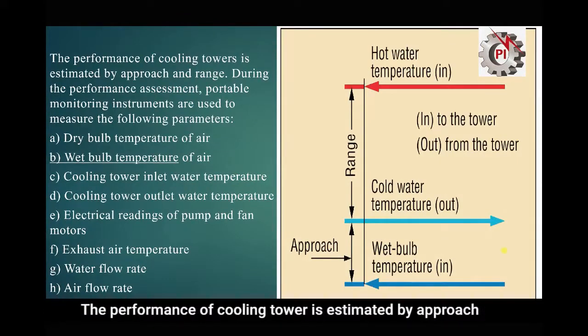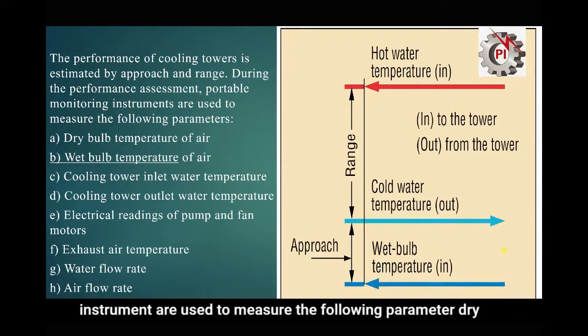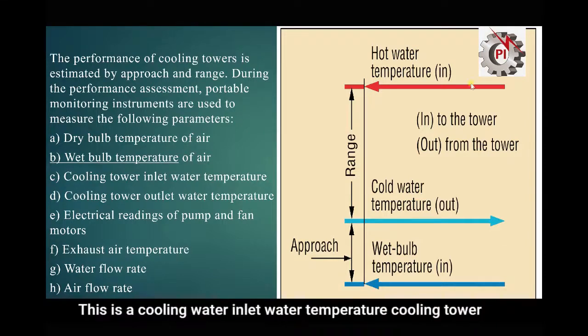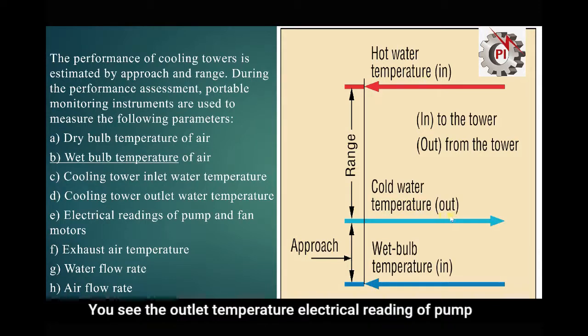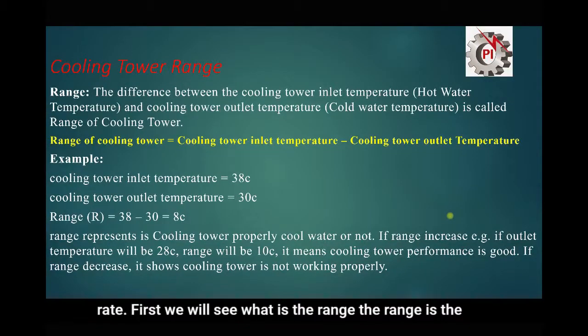The performance of a cooling tower is estimated by approach and range. During performance assessment, portable monitoring instruments are used to measure the following parameters: dry bulb temperature of air, wet bulb temperature of air, cooling tower inlet water temperature, cooling tower outlet temperature, electrical readings of pump and fan, exhaust air temperature, water flow rate, and air flow rate.